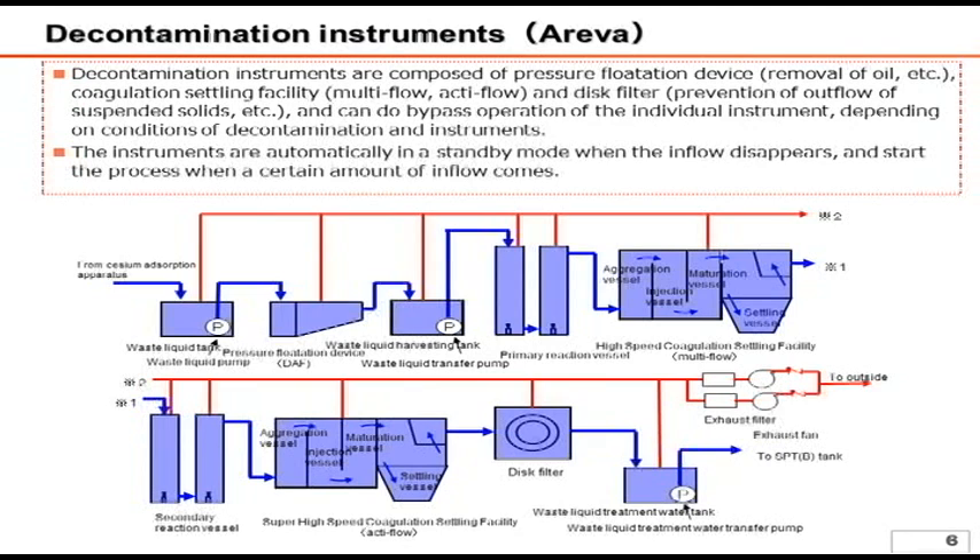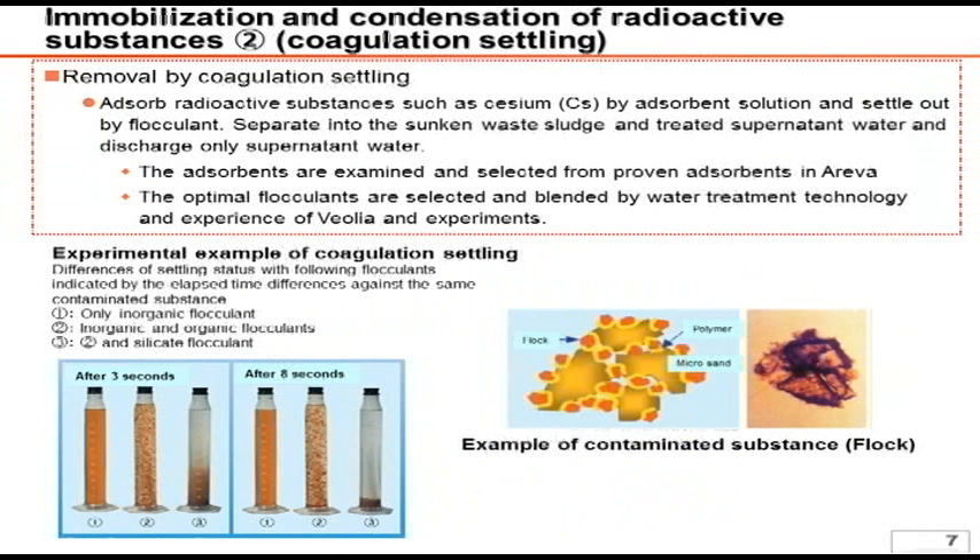The chemicals are added again to the clear supernatant water for further coagulation. After those treatments, the treated water is transferred to the SPT(D) tank shown on the right. The red line indicates the exhaust system using a fan in order to prevent a high concentration of hydrogen and oxygen inside the tanks, which may be produced due to radiation decomposition in the liquid treatment. Please refer to the next page for the detailed mechanism of this system. While we are not allowed to disclose detailed information regarding the chemicals, the coagulation settling method utilizes Areva and Veolia's water treatment technology, know-how, and chemicals.